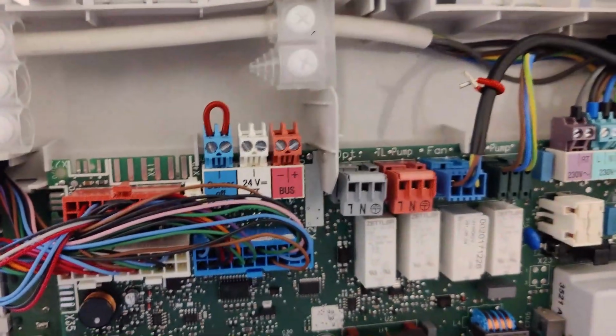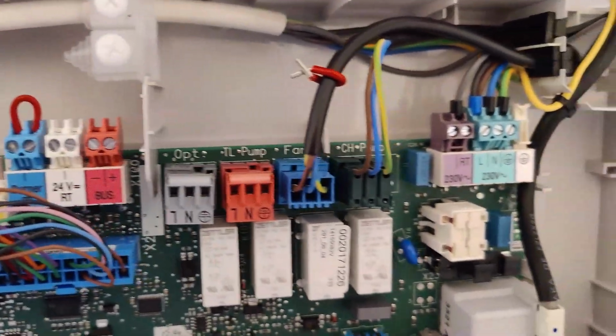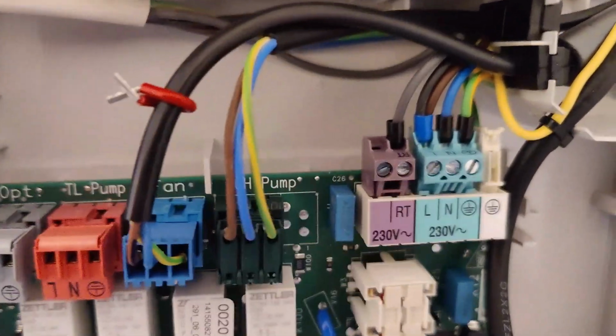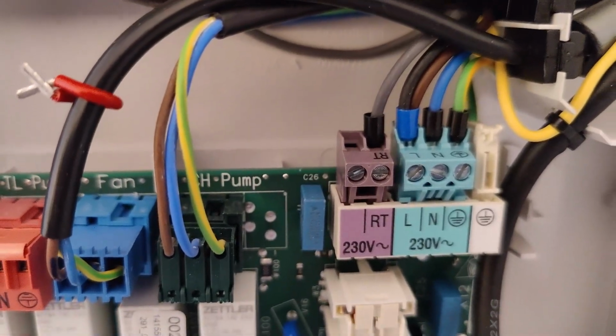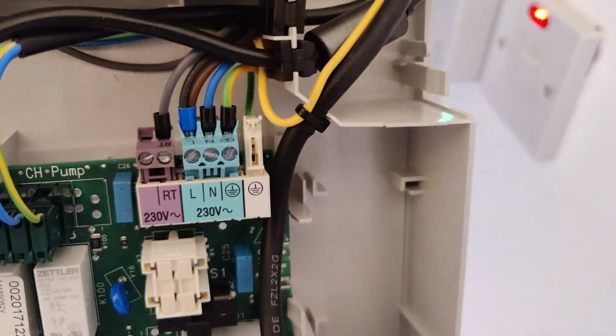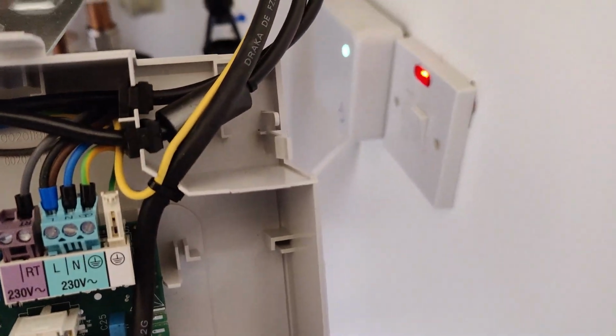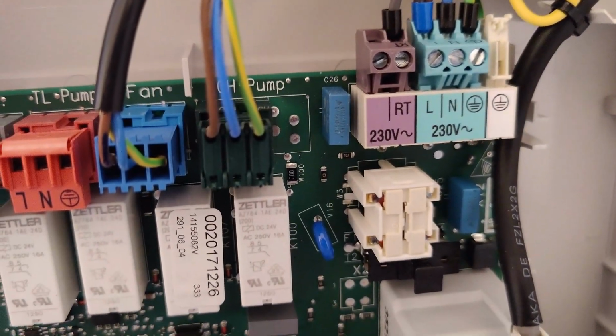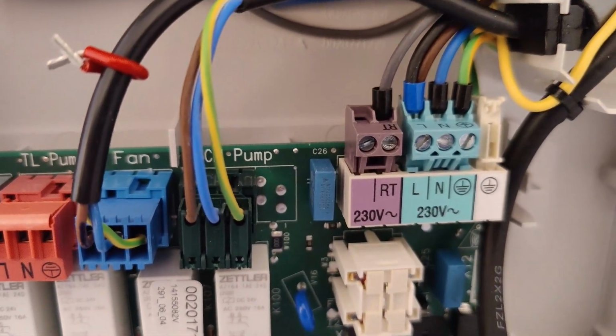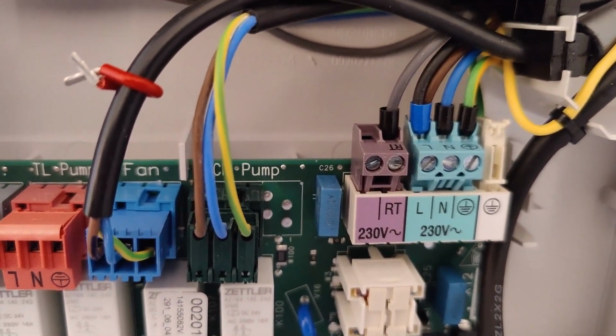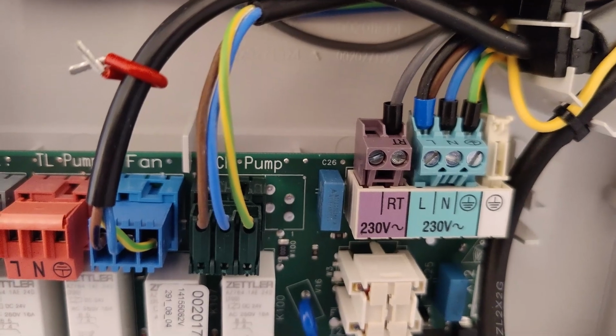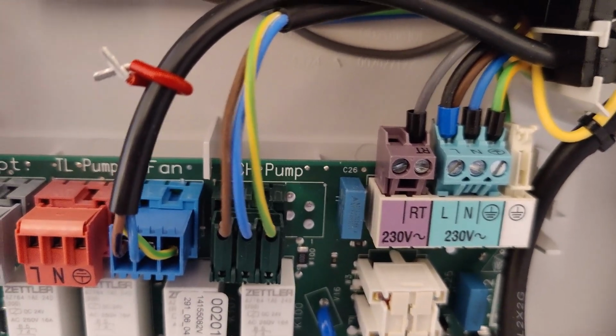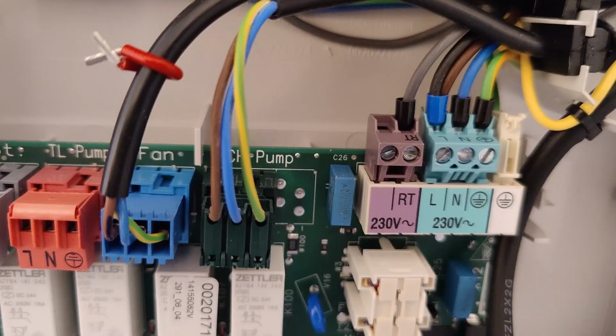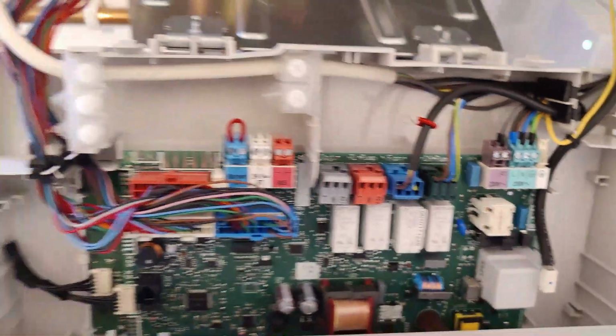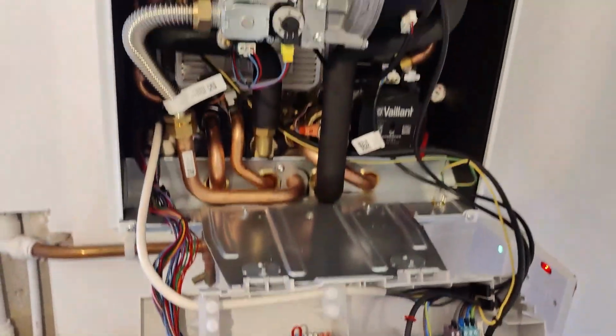And as you can see, I've only used a 5-core cable and I looped a live from here instead of looping it from there. So now basically the black is going to one side of the normally open switch, and grey is coming back from the other side of the same normally open switch. If you have any questions on that, just let me know.